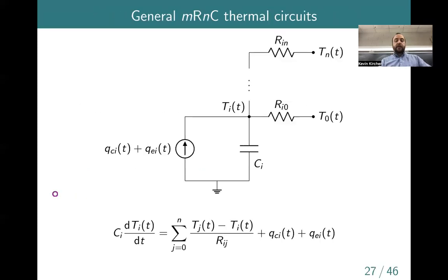Between air to air. Okay, so if we look back at this model, and we think of zone I, so maybe I is equal to 10 or something, and then N maybe is 100 here. So the heat transfer between the air in room 10 and the air in room, say 100, is basically given by the temperature difference, the delta T. So it's essentially Ohm's law, but for the thermal circuit. So it's delta T, which is like a change in voltage, a delta V in an electrical circuit model, divided by R, right? Where R is the thermal resistance between, say, apartment one and apartment number 100.